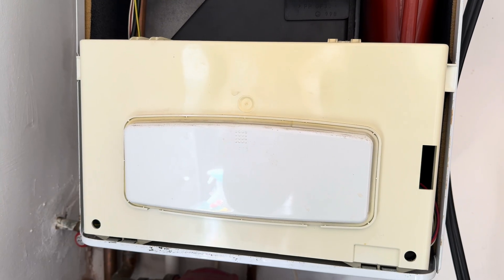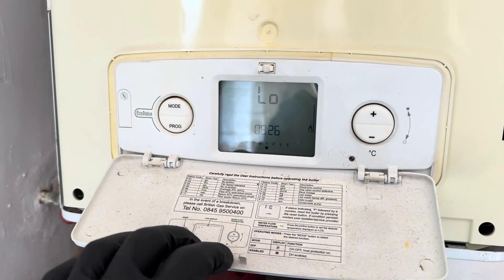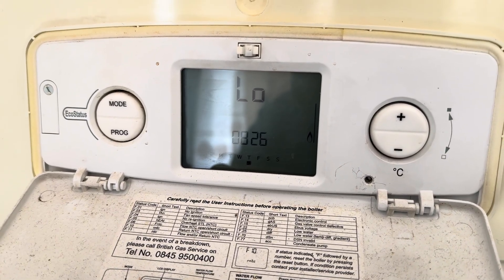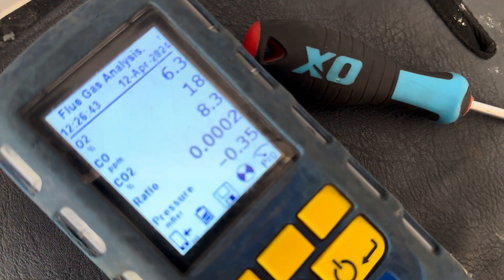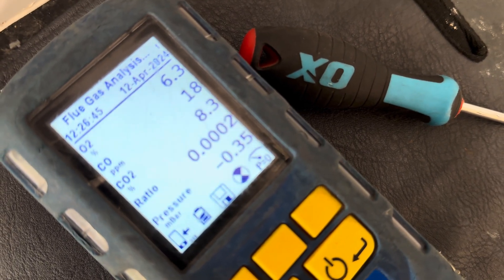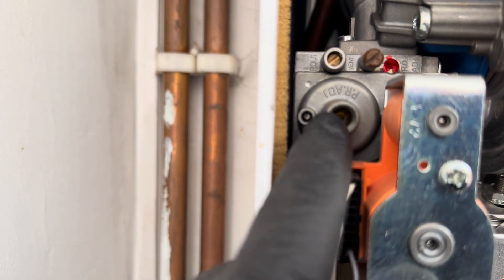So this is a Ideal Flexicom or a British Gas 330, it's making a noise. We put the boiler into low flame, then we adjust the readings. Apparently that's too low, so for the minimum we adjust using the offset, and the maximum we adjust using the throttle.